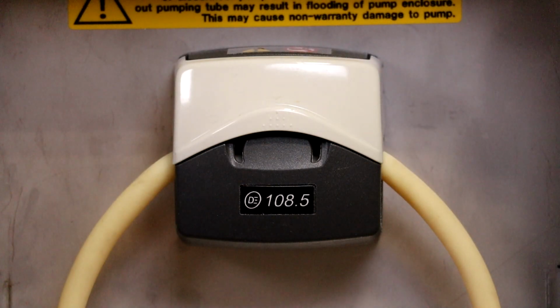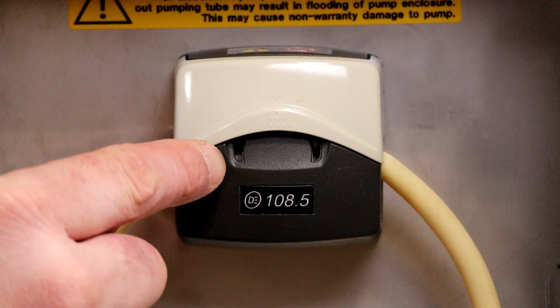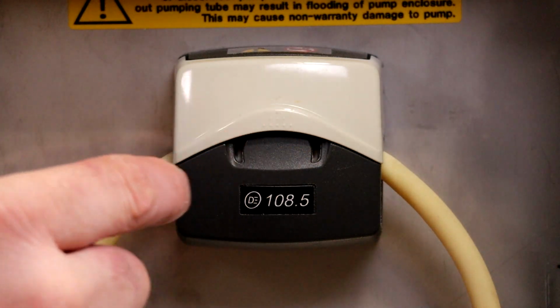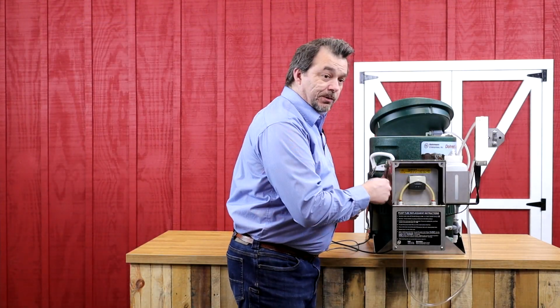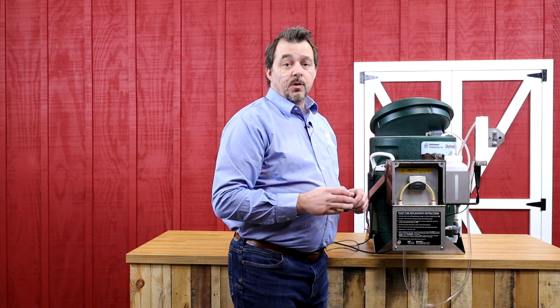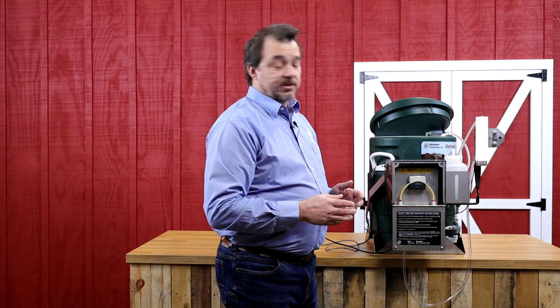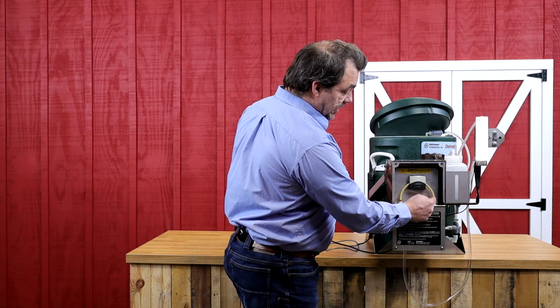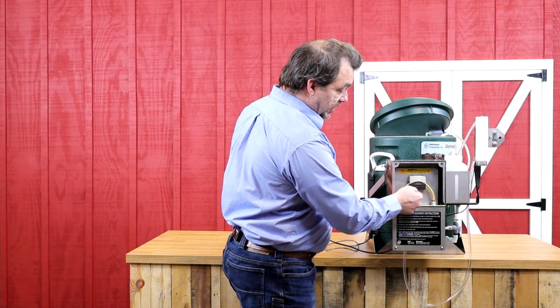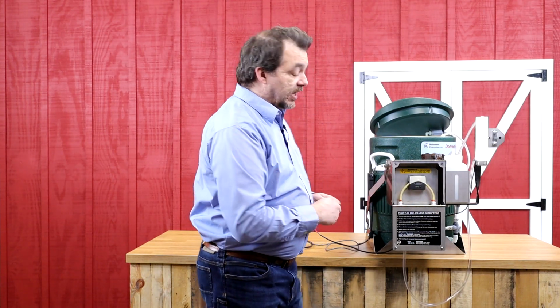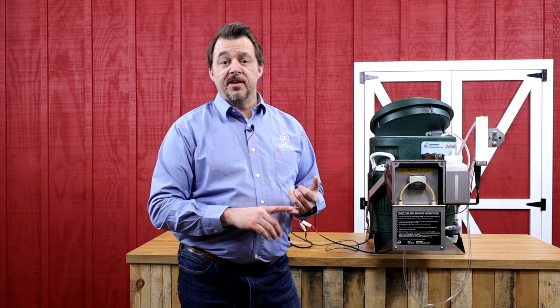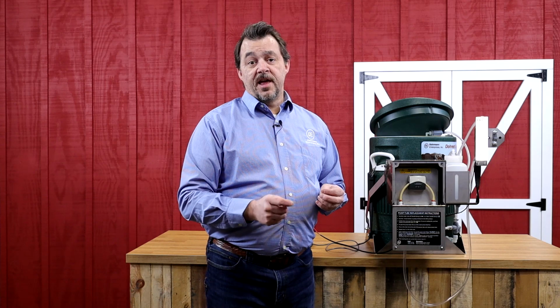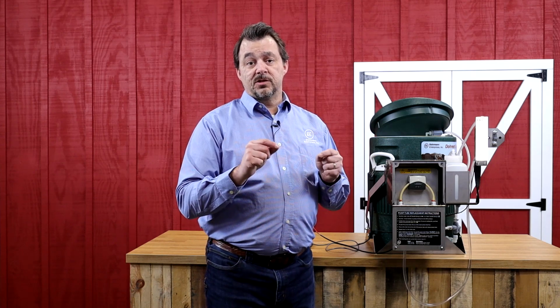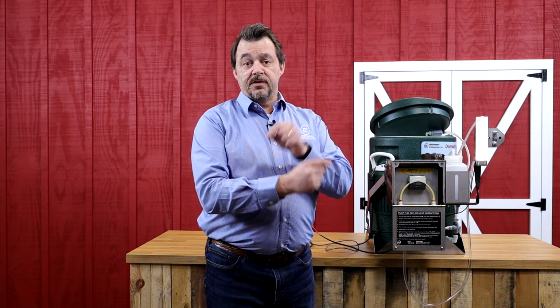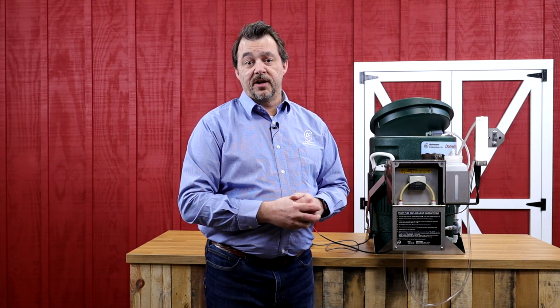And then we want to take a look. You can either look in these little holes to see your rollers going around, or if you want to, you can lift up the pump head and see which way the rollers are turning. The rollers need to be turning counterclockwise because this is our input side and this is our output. So the pump is rotating in a counterclockwise direction. If it's rotating counterclockwise, then we know everything is wired correctly. If it is rotating clockwise, then we need to go to the power supply and reverse the wires. We need to switch the positive and ground around to make sure that we've got the polarity correct.